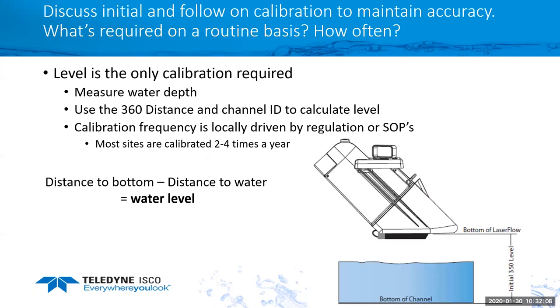As far as when you install a laser flow sensor, the only calibration required for that is the level, the depth calibration.